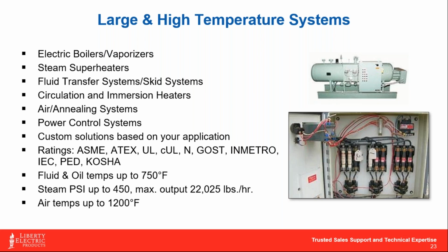Some of the big advantages to this, again, are that they don't create noise aside from the humming, and there's no fuel piping in or emissions out of the unit itself. When you've got predictable wear factors, like, again, testing your elements for resistance and being able to pretty much predict your preventive maintenance schedules on these, it certainly creates an application for a lot less downtime versus mechanical systems that could pretty much break at any given time.